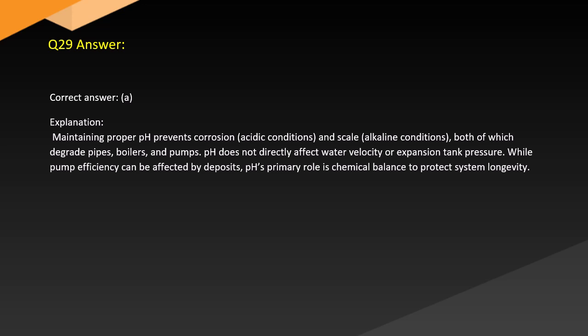Answer. Correct answer, A. Explanation. Maintaining proper pH prevents corrosion in acidic conditions and scale in alkaline conditions, both of which degrade pipes, boilers, and pumps. pH does not directly affect water velocity or expansion tank pressure, while pump efficiency can be affected by deposits. pH's primary role is chemical balance to protect system longevity.